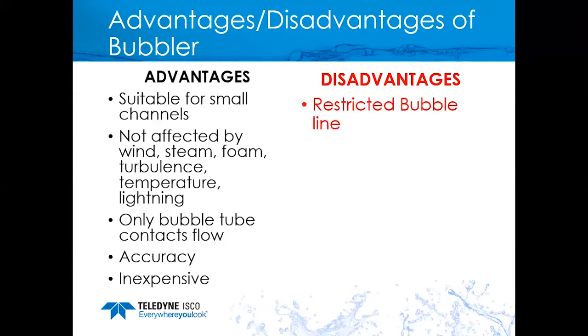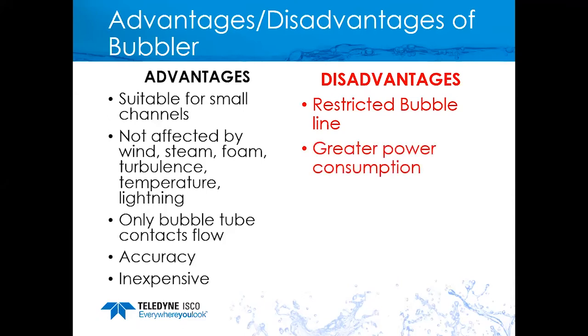Disadvantages of the bubbler include the potential for restricted bubble lines. If there's a lot of sediment or silt, it could plug the end of the line. ISCO flow meters have an automatic purge system to help clear restrictions, but sometimes maintenance is required — cleaning out debris or running a wire through the bubble line. Bubblers can also have greater power consumption, especially with long lines where the air pump turns on frequently due to excessive purging, potentially using more power than an ultrasonic sensor.